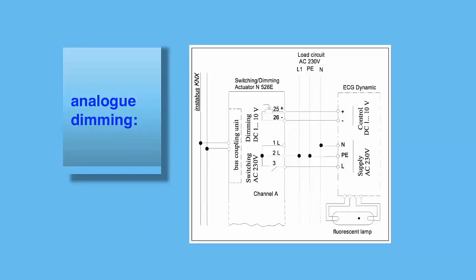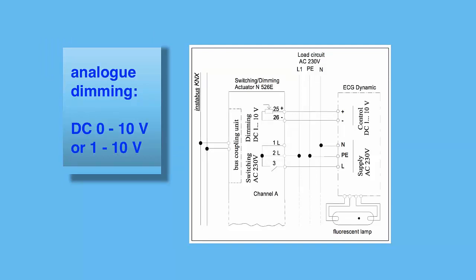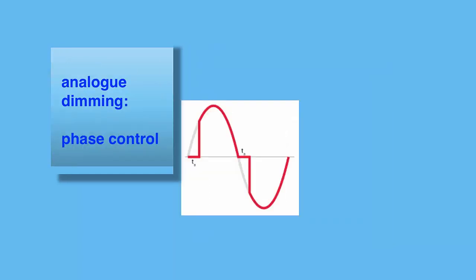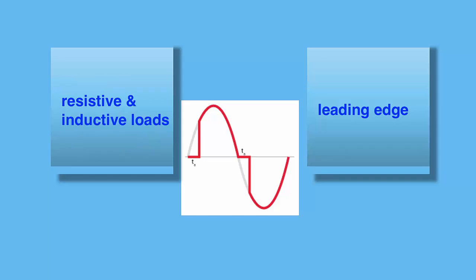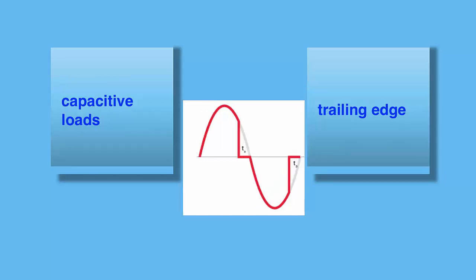Analog dimming is either based on a DC control voltage for the ballast ranging between 0 and 10 volts — active or passive, in this case 1 to 10 volt — or a phase control of mains power, which can be either leading edge (inductive and resistive loads, magnetic transformers and incandescent bulbs) or trailing edge (electronic transformers, capacitive loads).